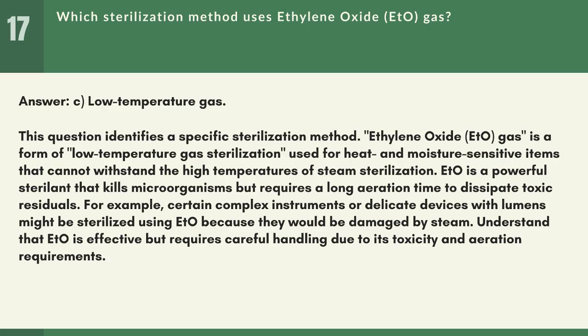ETO is a powerful sterilant that kills microorganisms but requires a long aeration time to dissipate toxic residuals. For example, certain complex instruments or delicate devices with lumens might be sterilized using ETO because they would be damaged by steam. Understand that ETO is effective but requires careful handling due to its toxicity and aeration requirements.